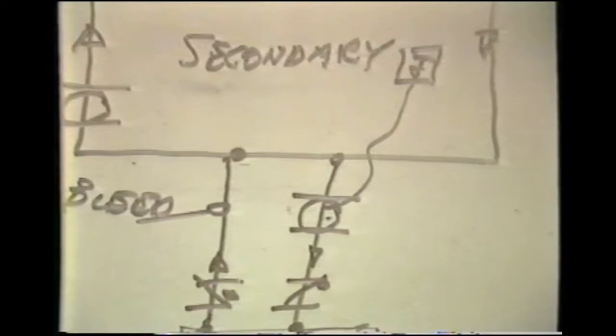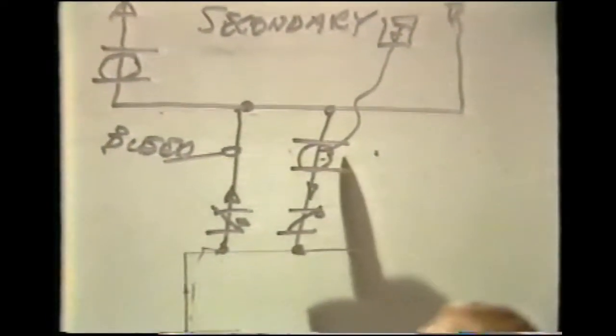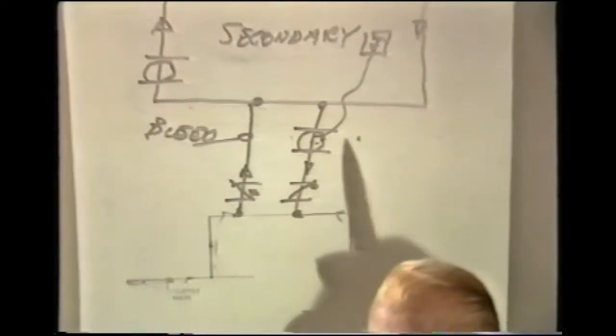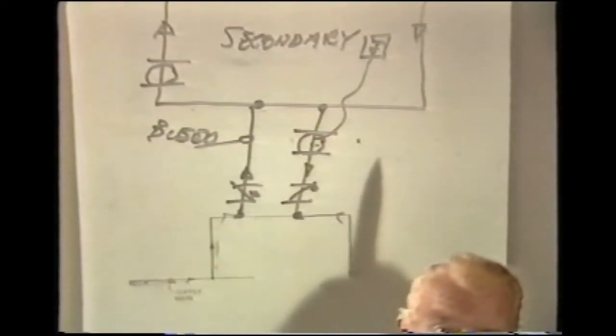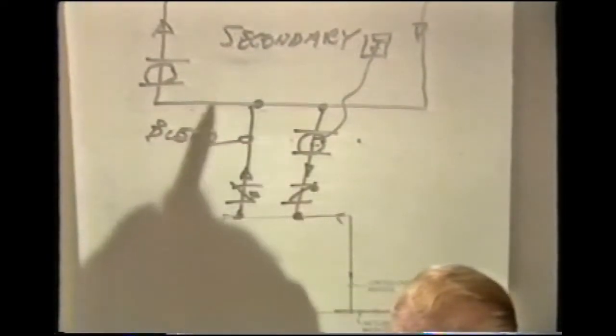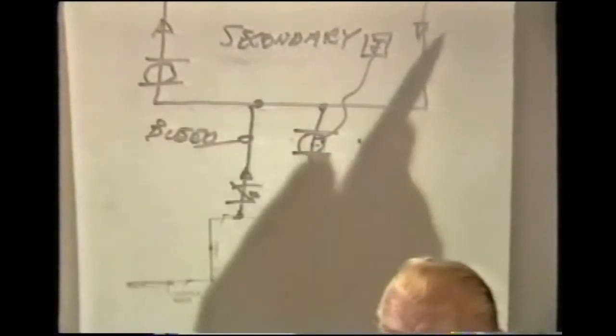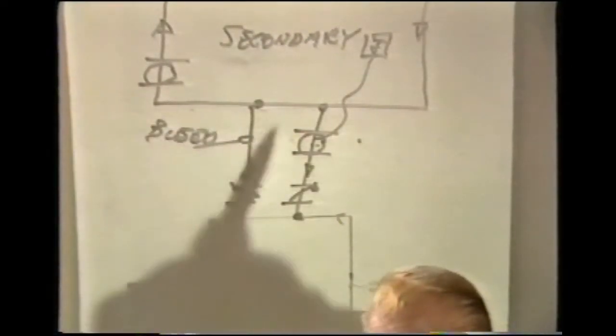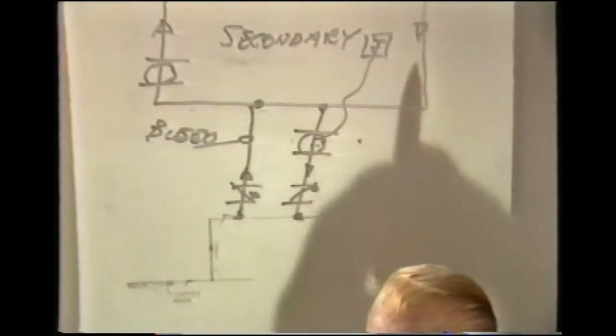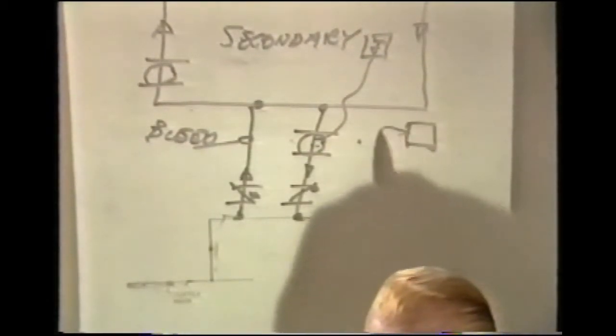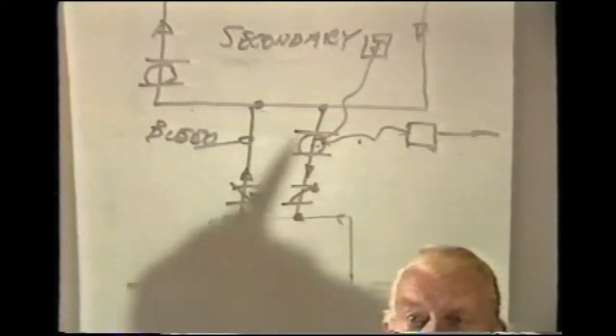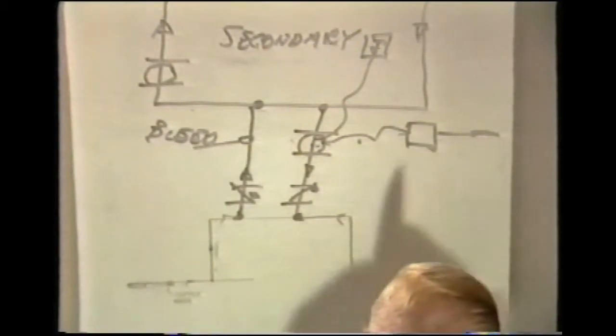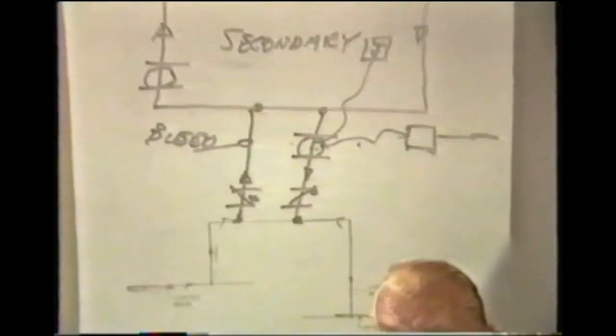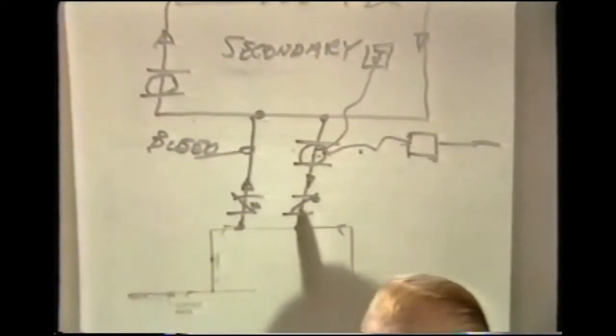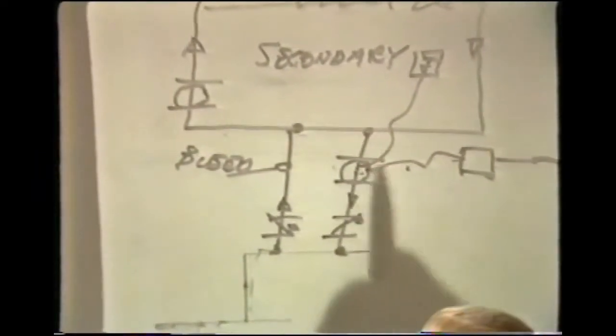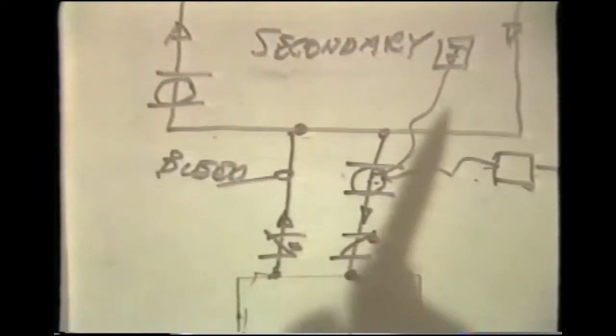The manner in which this will work will be that the pump will cycle, and will cycle relatively frequently, depending on the load, of course. We can, of course, provide reset for a comfort heating application by a reset control, indoor-outdoor, applied to the pump. So let's go through this example then and determine as the flow rate need we may have for the injection pump as contrasted with the secondary circuit.